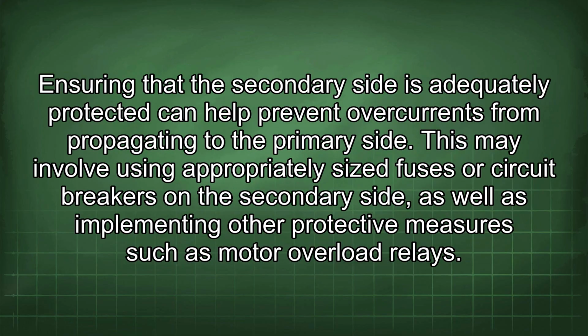Ensuring that the secondary side is adequately protected can help prevent overcurrents from propagating to the primary side. This may involve using appropriately sized fuses or circuit breakers on the secondary side, as well as implementing other protective measures such as motor overload relays.